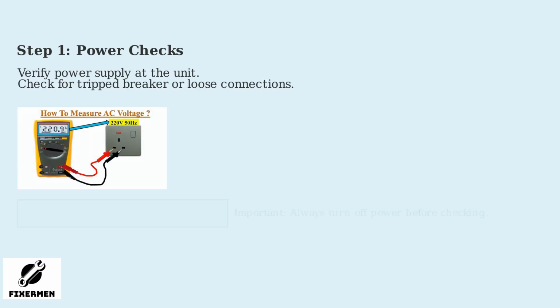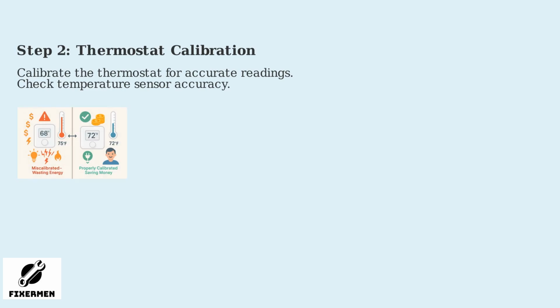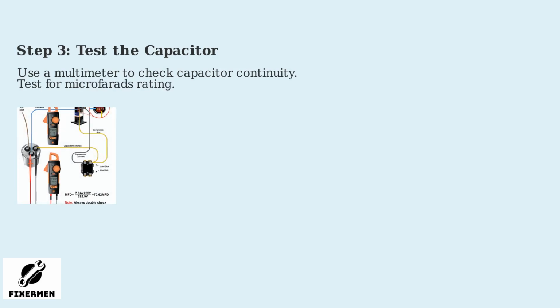Start by checking the power supply to the Trane XR15 unit. Ensure the breaker isn't tripped and connections are secure. Use a multimeter to verify voltage at the unit. Next, calibrate your thermostat. A miscalibrated thermostat can prevent the unit from starting. Compare the thermostat reading with a separate thermometer. Test the run capacitor with a multimeter. Check for continuity and verify the microfarads rating matches specifications. A faulty capacitor often causes startup failures.